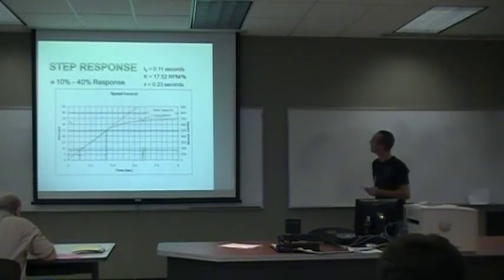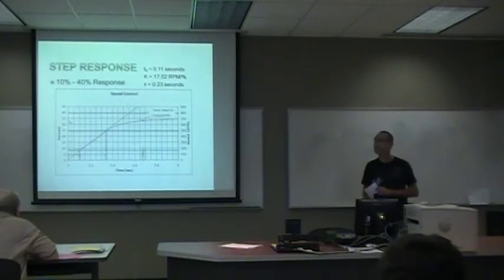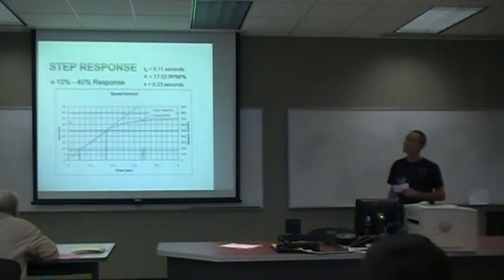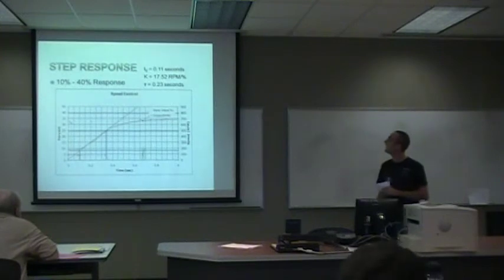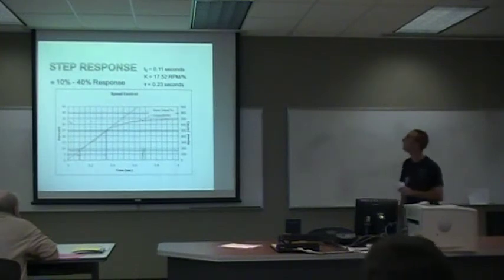And this is the sample speed response graph for the lower region between 10 percent and 40 percent, with the dead time of 0.11 seconds, the gain of 17.52 RPM per percent, and a time constant of 0.23 seconds.